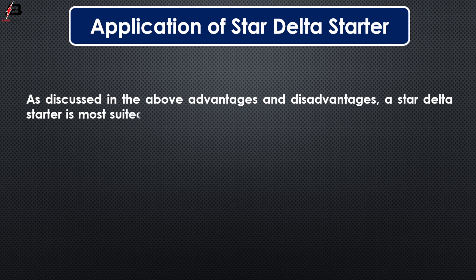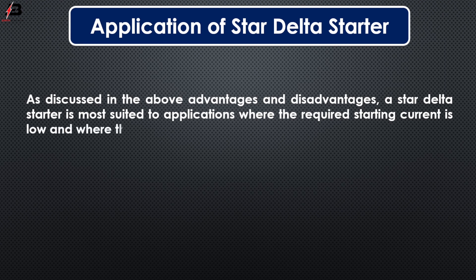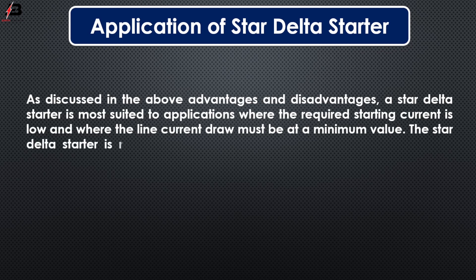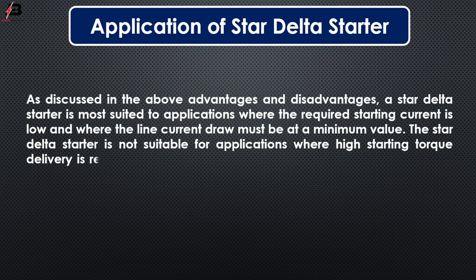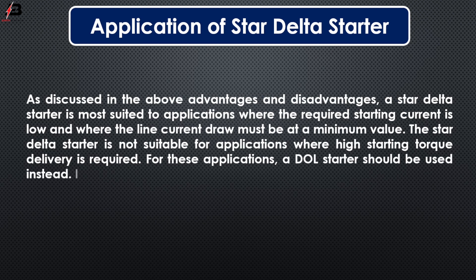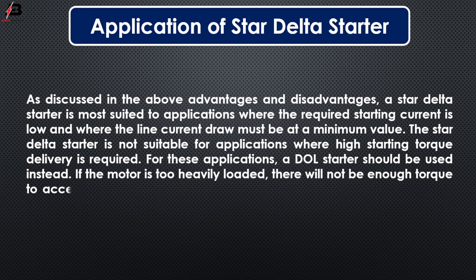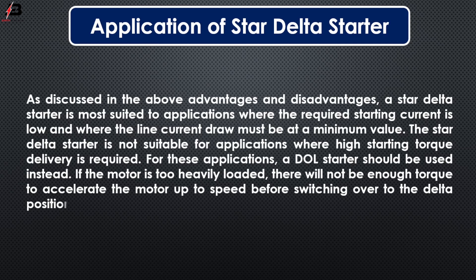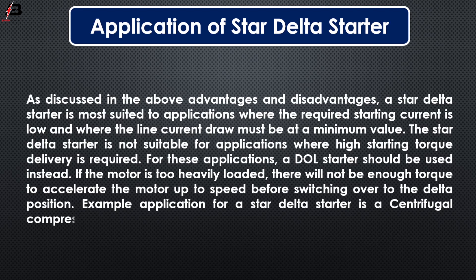Applications of star delta starter: As discussed in the advantages and disadvantages, a star delta starter is most suited to applications where the required starting current is low and where the line current draw must be at a minimum value. The star delta starter is not suitable for applications where high starting torque is required. For these applications, a DOL starter should be used instead. If the motor is too heavily loaded, there will not be enough torque to accelerate the motor up to speed before switching over to the delta position. An example application for a star delta starter is a centrifugal compressor.